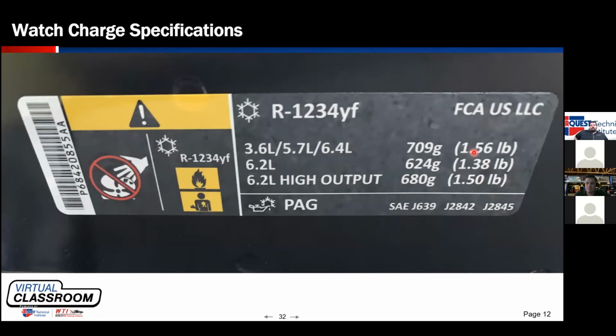So what's going to happen, Brent, if we take that 6.2 and charge it to the 6.4 spec? So instead of putting 1.38 pounds of refrigerant in it, we put 1.56 pounds of refrigerant in it. It's not going to perform right. The pressures are going to be off. Yep, we've got an overcharge. We've got close to a 10%, maybe a little over a 10% charge difference. Conversely, if we take that 6.4 and charge it to 6.2 spec, it's not going to cool. We've got a system that's undercharged.